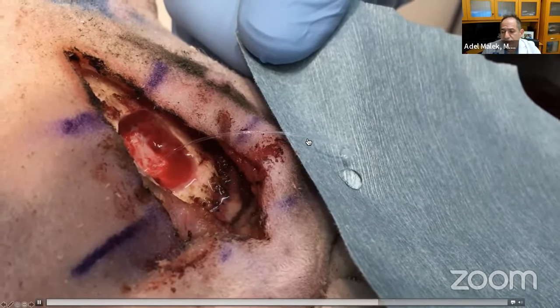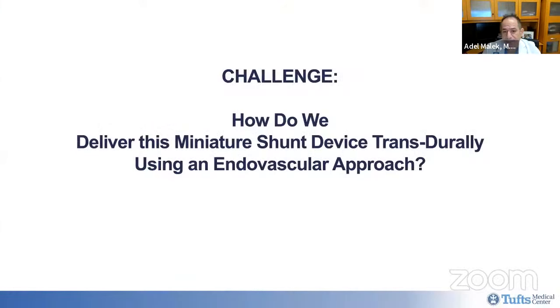This is the actual tubing. Although the ID is very small, around 0.165, pretty much like a typical microcatheter for aneurysm coiling, the distance is very short compared to our VP shunt tubing. So the resistance is actually pretty low, and you get very good flow.